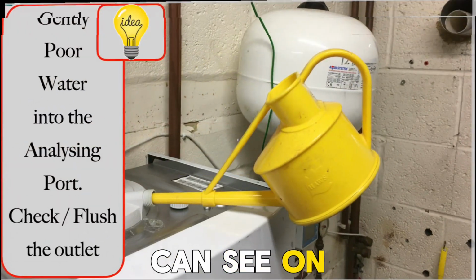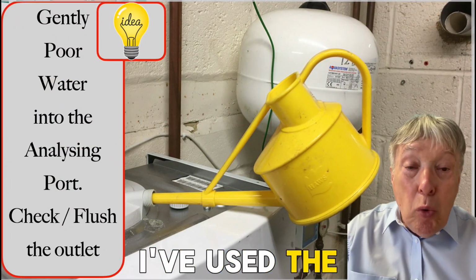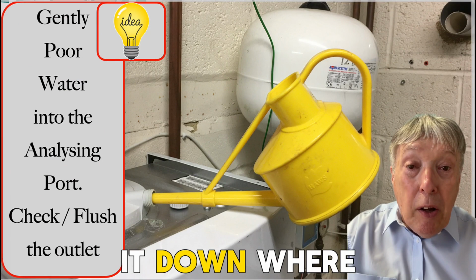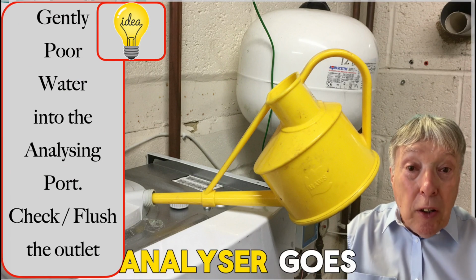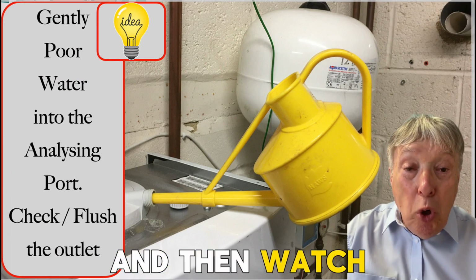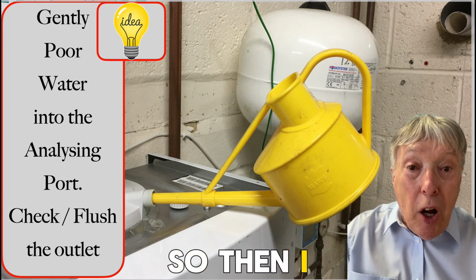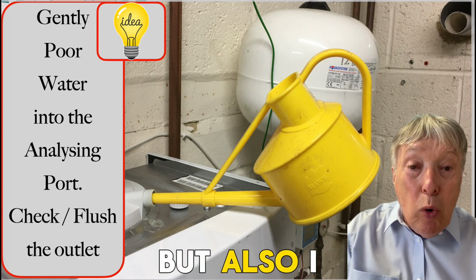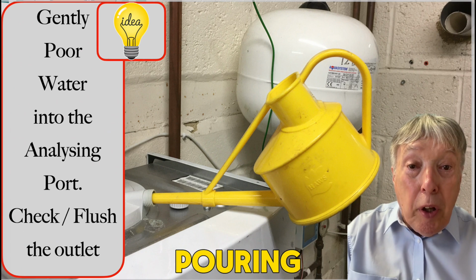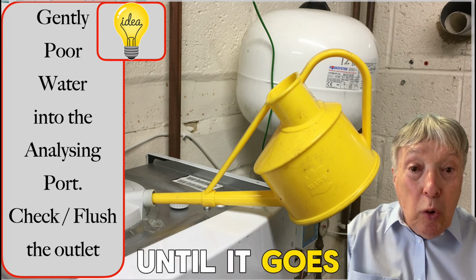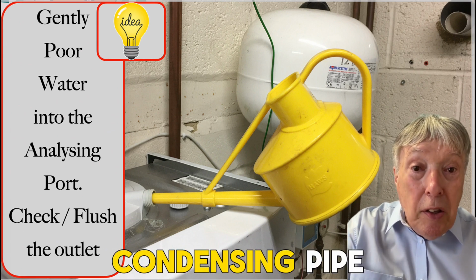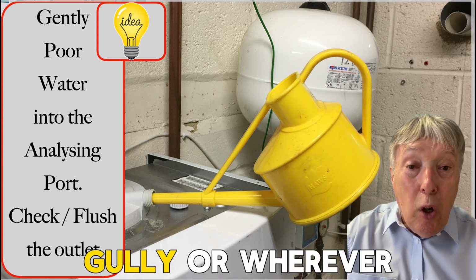And as you can see on this picture here, I've used a watering can, and I pour it down where the gas flue analyzer goes, and then watch the trap fill, so then I know it's not blocked. But also I keep pouring and pouring until it goes right through the condensing pipe out to the gully or wherever.